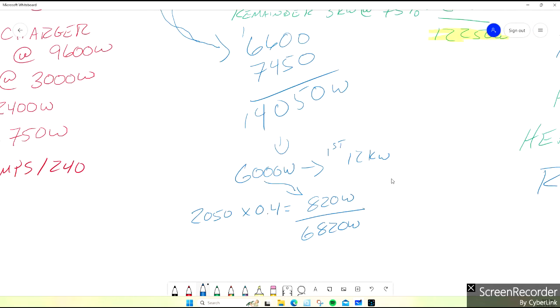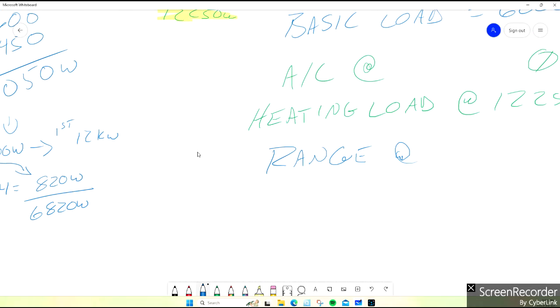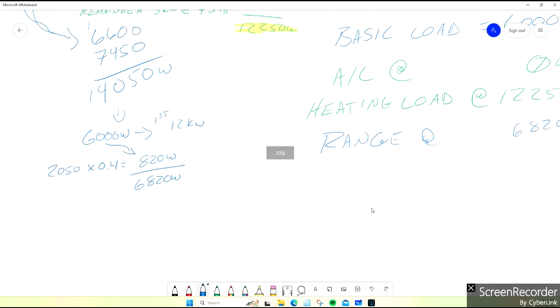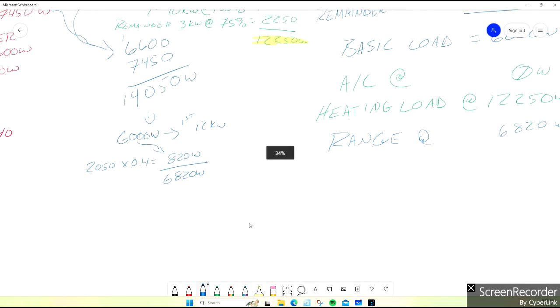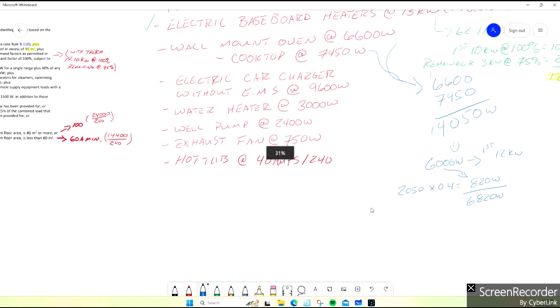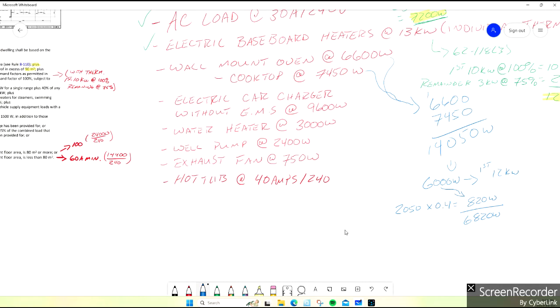I'll put that over here, 6,820. Again, it's because typically your burners and ovens are not all on at the same time, right? The only time it's really happening is around the holidays.